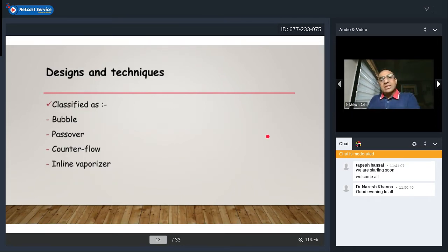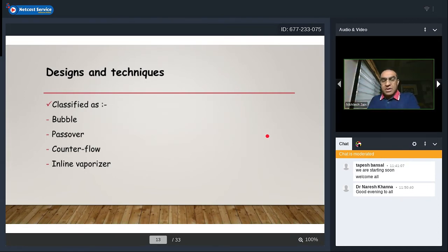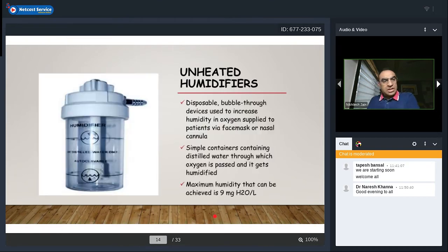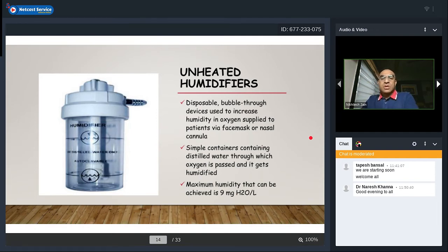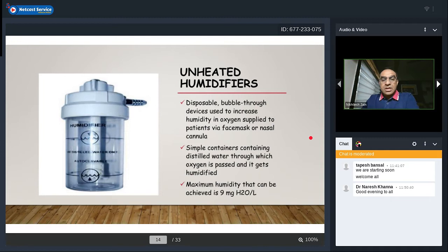Various humidifier designs exist: bubble, pass-over, counter-flow, and inline vaporizer. Unheated humidifiers are disposable bubble-through devices used to increase humidity in oxygen supplied via face mask or nasal cannula — simple containers of distilled water through which oxygen is passed to get humidified. The maximum humidity achievable through these is approximately 9 mg of water per liter.